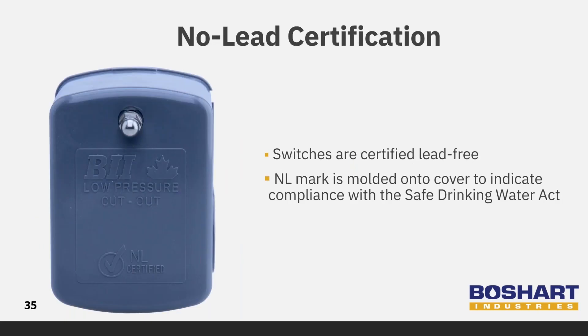Many import switches are not certified to ensure compliance with the reduced lead content requirements. They are also often missing lead-free markings on the cover. Boshart switches are no lead certified to NSF 372 standard. The covers have a large no lead certification mark, making identification of compliance to the Safe Drinking Water Act easy for inspectors. The no lead certification listing number is written inside the cover, along with CSA and UL electrical listings.